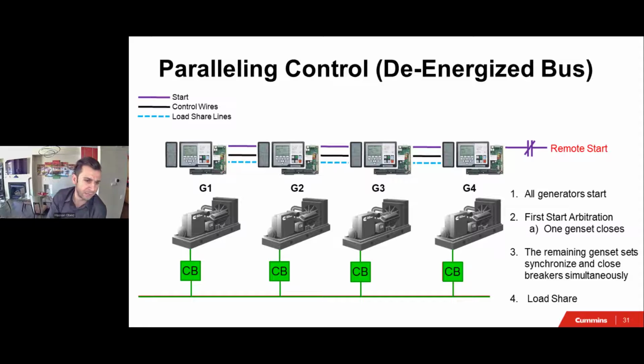The first start arbitration dictates which one of them goes first. Since there's no master level controller to orchestrate the system, the generators do this arbitration, and one of them wins, and that one closes its circuit breaker to the bus. The others are always monitoring this load side, and they can close immediately after, all simultaneously, after the first one closes. Now their magnetic fields are coupled, and we go into load share, where the voltage and the frequency are constantly adjusted to match as the load varies.